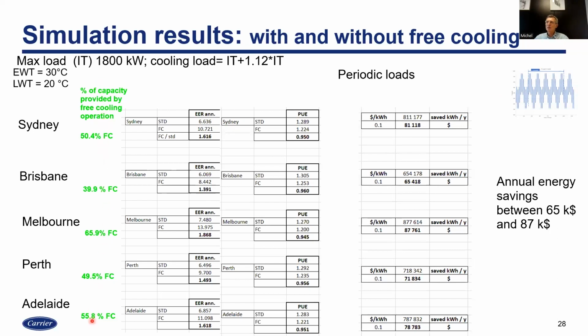What is the amount of capacity provided by free cooling depending on location? I'm talking about energy rejected to the air without operating the compressor. We see this is 50% in Sydney, 40% in Brisbane, 65% in Melbourne, 49% in Perth, and 55.8% in Adelaide. It's a function of temperature, for sure.